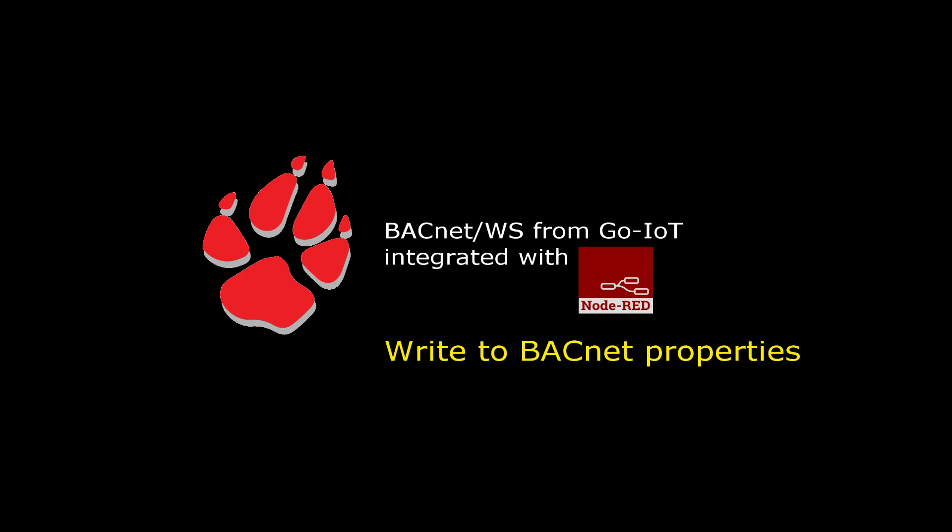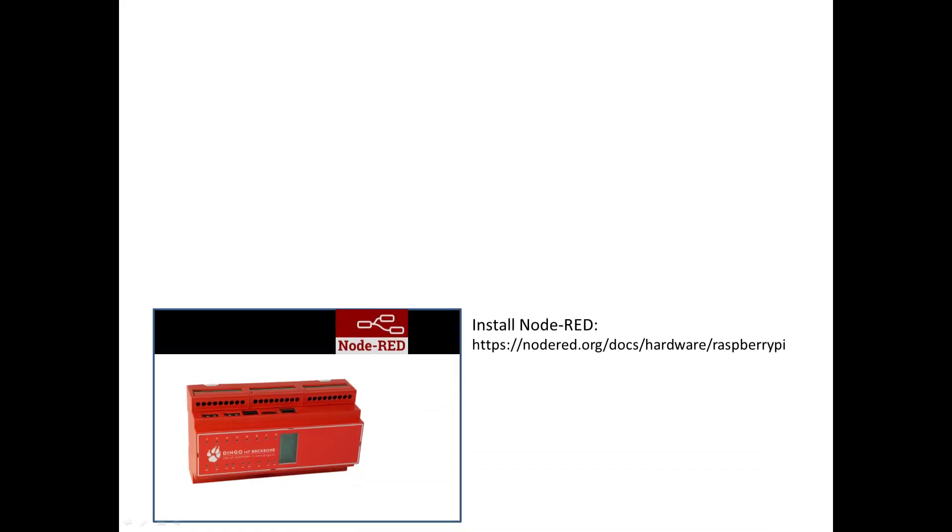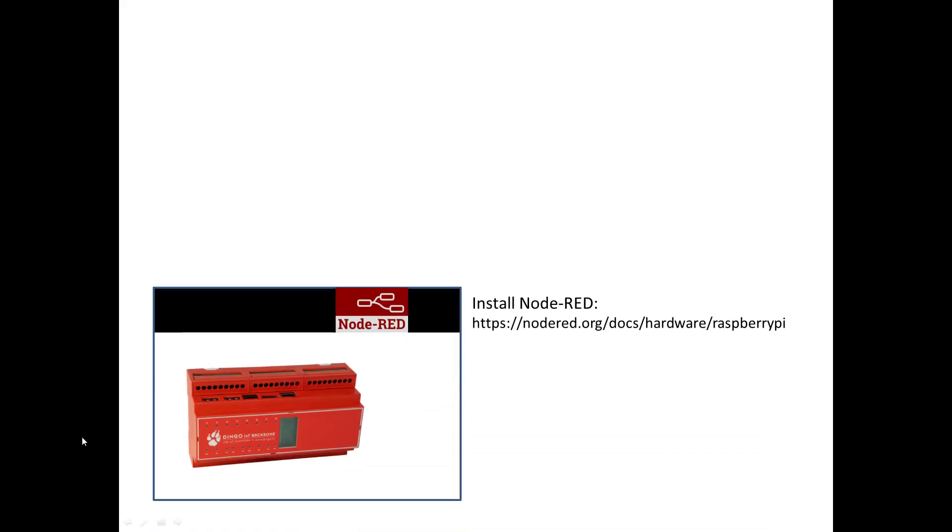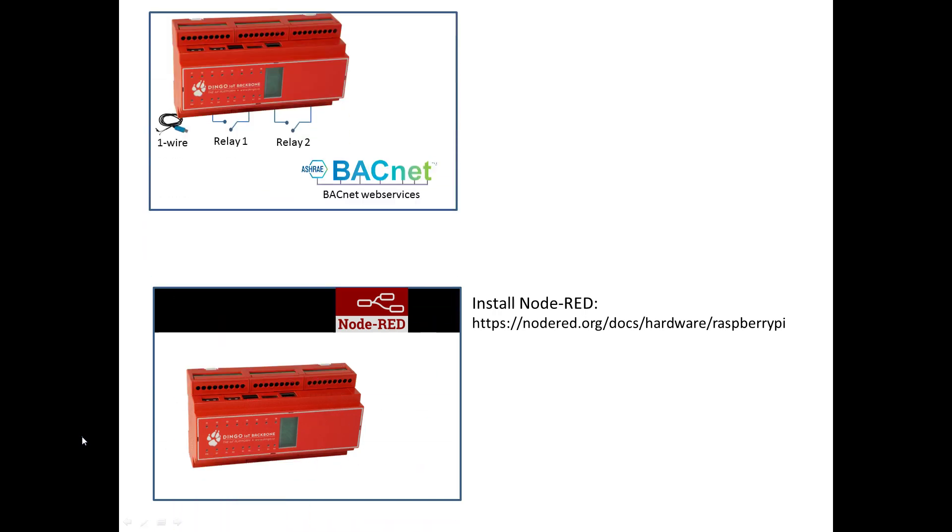In this demonstration we will focus on writing values to a BACnet property. The Dingo device comes with two relays installed on its baseboard. In this demonstration there is nothing connected to those relays, but I can still read whether the relay is on or off, and I can turn it on and off by writing to the BACnet objects that are associated with the relays.